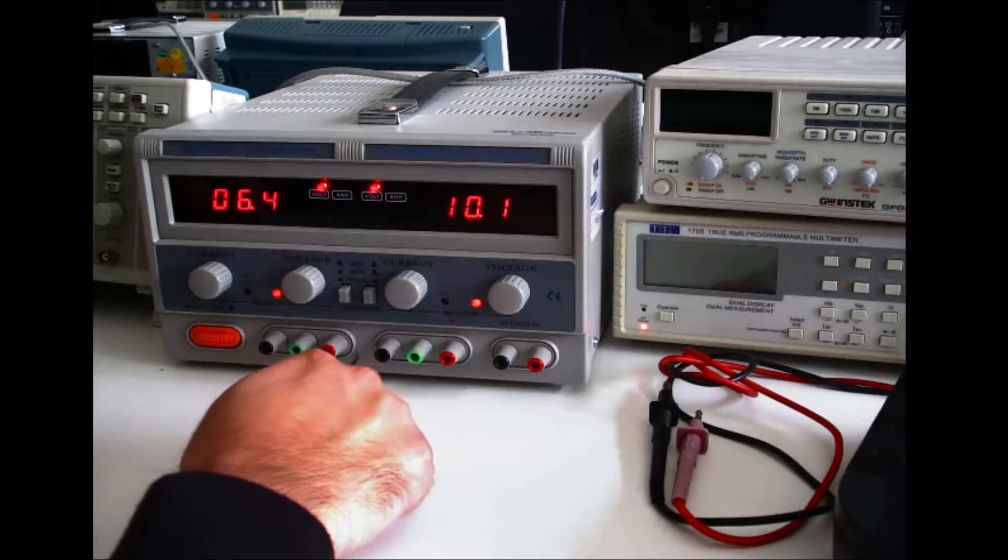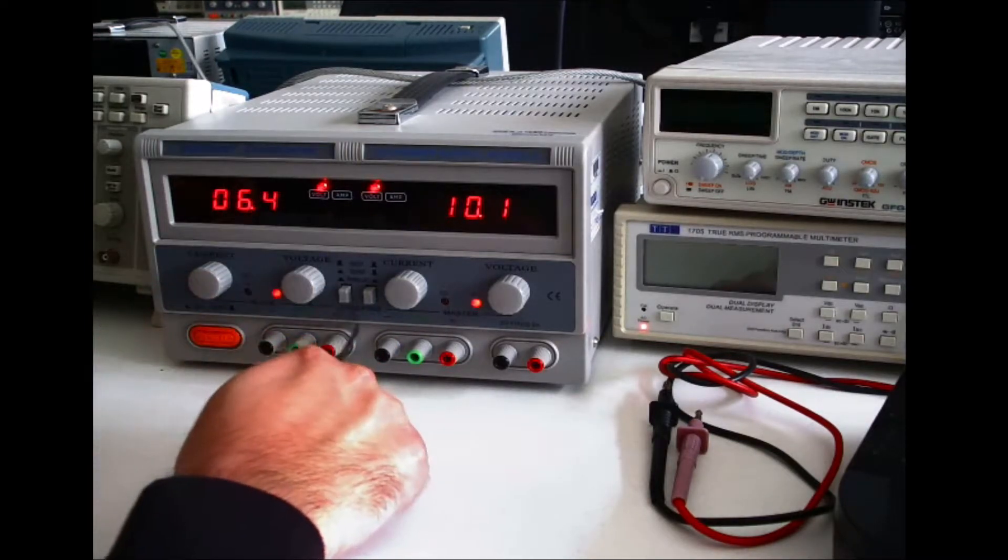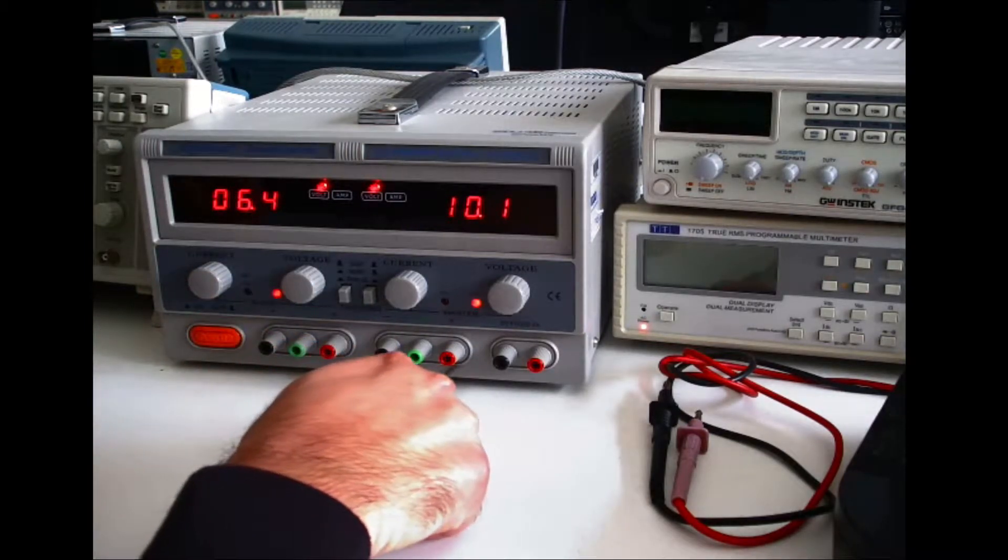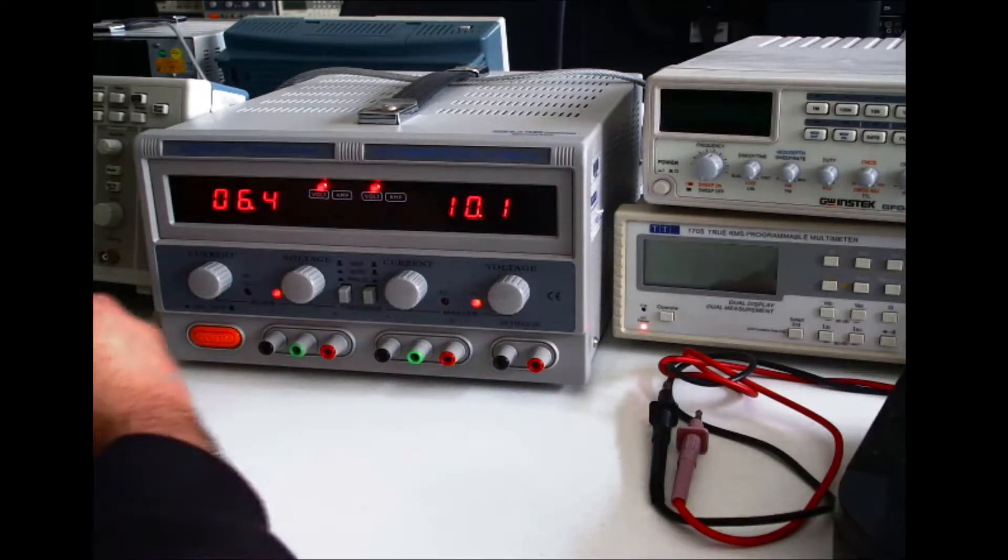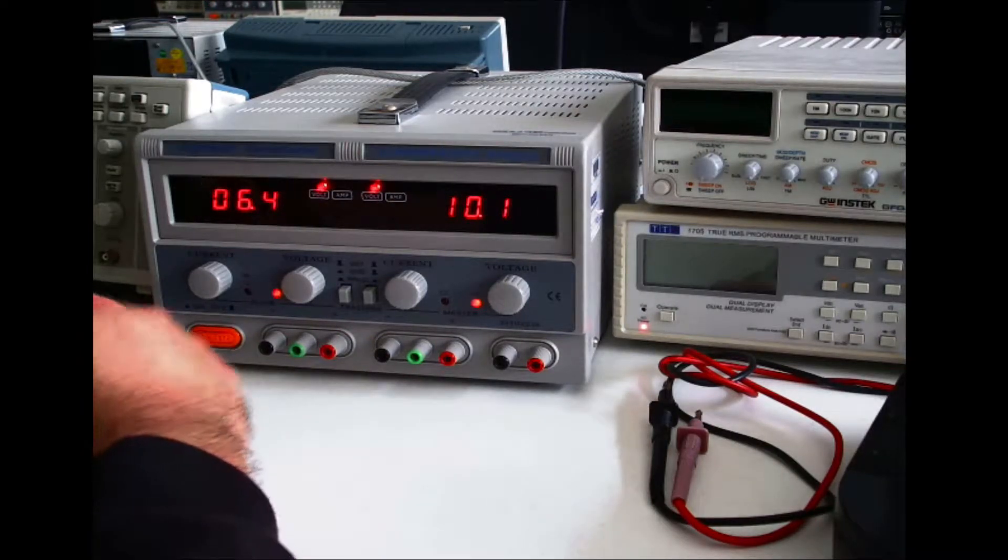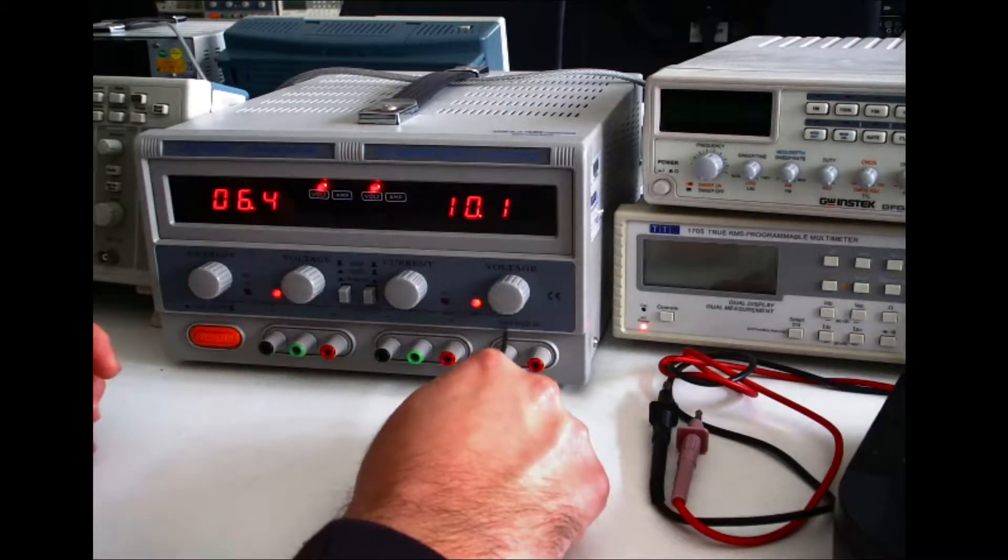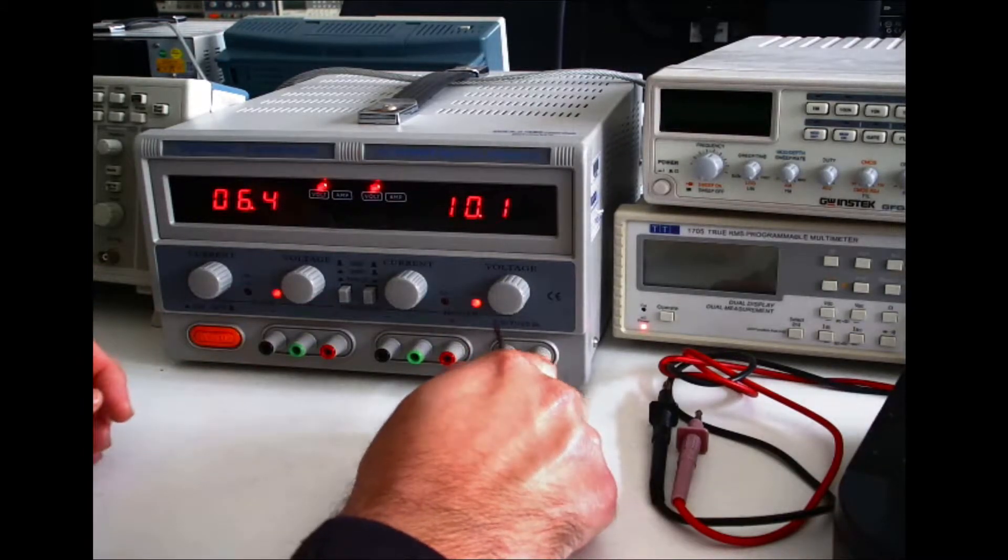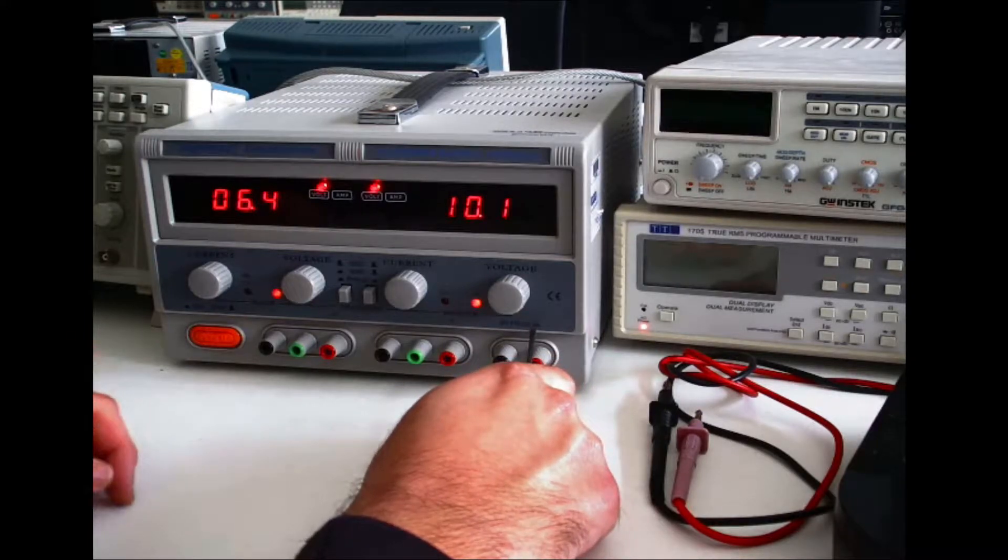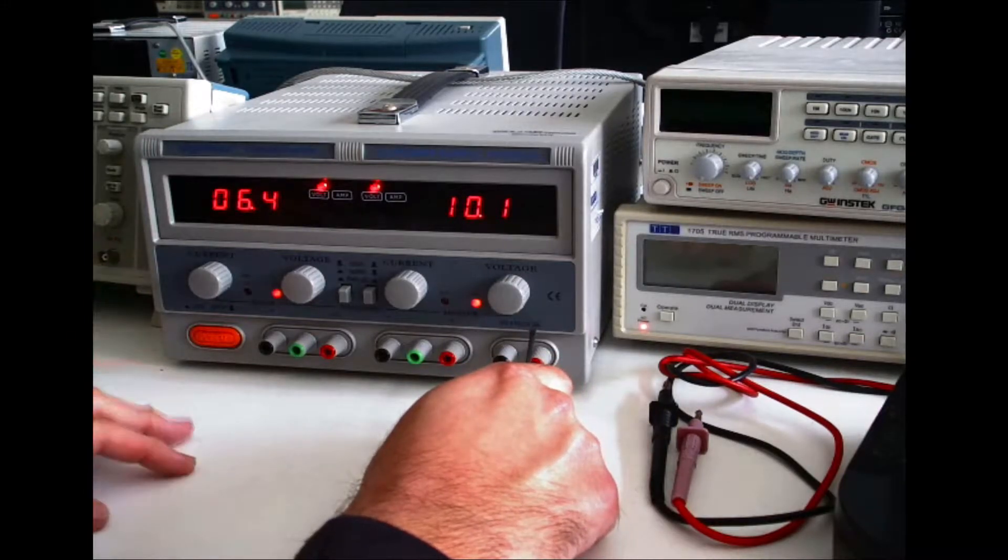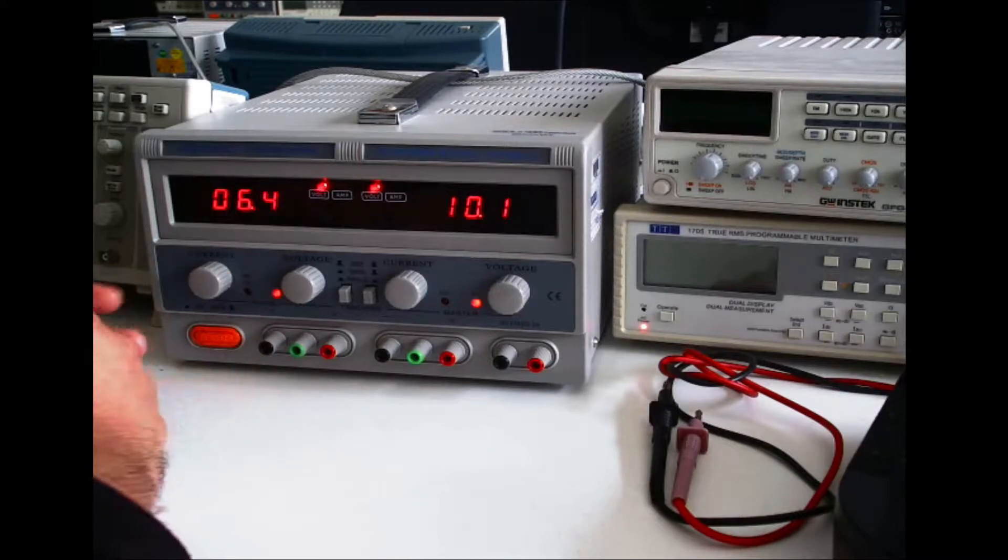In its current configuration each power supply is set up to be working independently and this power supply will always provide 5 volts with a fixed output with a maximum output current of 3 amps.